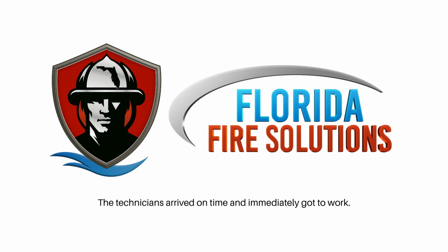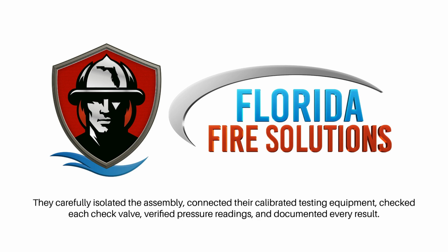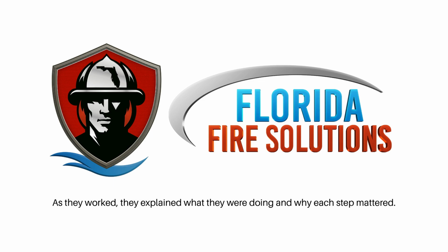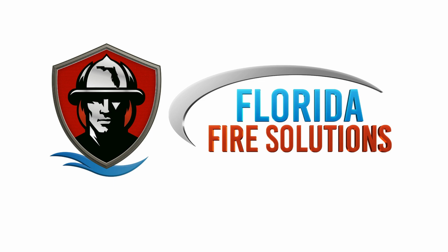The technicians arrived on time and immediately got to work. What impressed me was how methodical the process was. They didn't rush through the testing just to generate paperwork. They carefully isolated the assembly, connected their calibrated testing equipment, checked each check valve, verified pressure readings, and documented every result. As they worked, they explained what they were doing and why each step mattered.